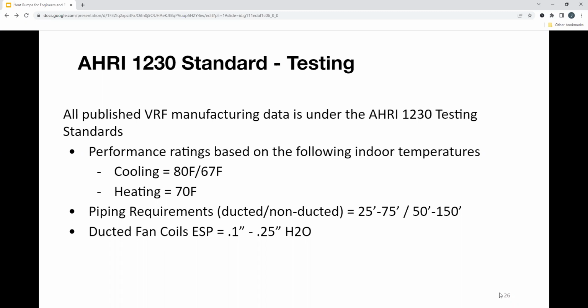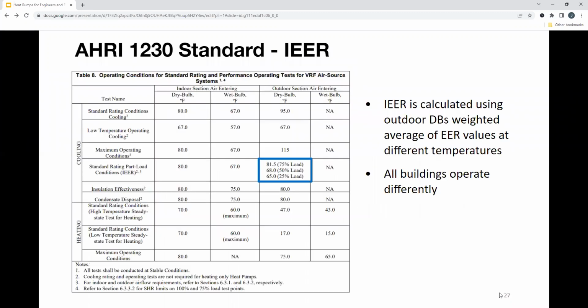Looking at the indoor temperatures, we're always going to see cooling mode tested at 80 degrees and 67 degrees, and then heating is going to be 70 degrees. So if you're looking through our submittals, those are the nominal capacities you're going to be seeing, because that is our tested data, right? They also use certain piping requirements depending on if it's ducted or non-ducted, anywhere from 25 feet to 75 feet, or for non-ducted up to 150 feet. And then we set certain external static pressures as well, anywhere from 0.1 inch to 1/4 of an inch. So whenever you see VRF data, heat pump data, this is the testing that it conforms to.